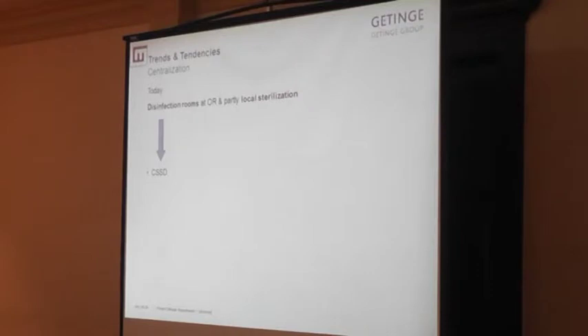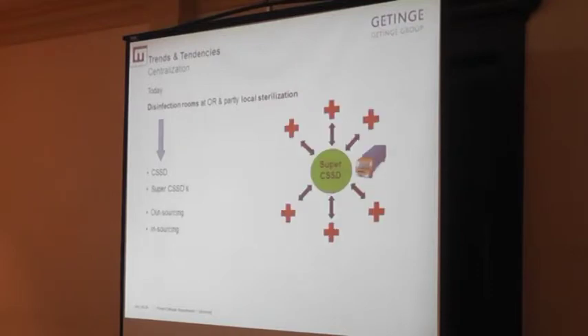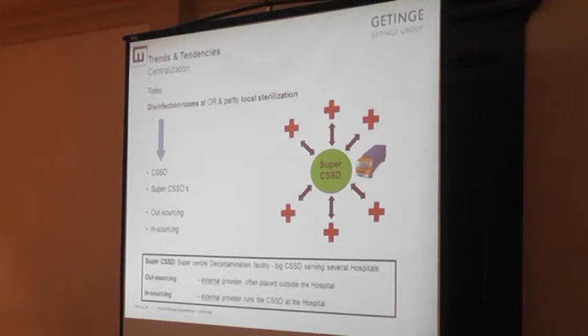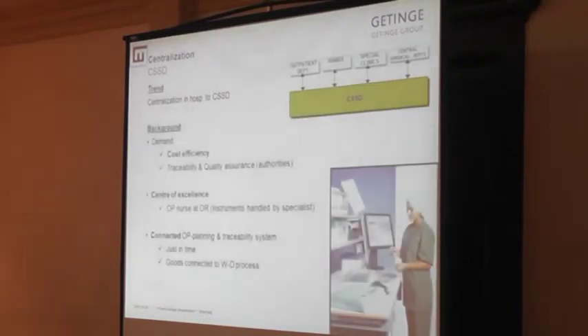First, it's been quite common to wash at the OR, but now we move over to wash at the CSSD, centralizing. We do it in one spot, because it is cost efficient to do it in one spot. We utilize the washer more. And we also have some demands from authorities with traceability. So if somebody gets sick, the traceability system proves that it was a good process, that the process was approved. We can go back from the patient to the system and see that it was approved, it was good. You can even see the temperature curve in the sterilizer and washing.